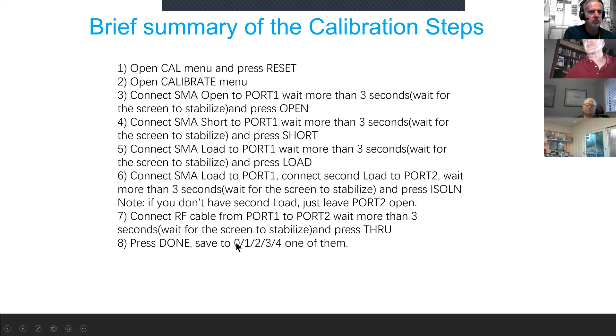And then connect an SMA load to port 1 and another to port 2, wait a few seconds, and press isolation. That second load isn't absolutely essential unless you're trying to measure a high isolation device. So if you don't happen to have a second load, just leave port 2 open. You connect an RF cable from port 1 to port 2 and wait a few more seconds and press through. Press done and save the data to one of the calibration registers 0 through 4. And there you are, you're calibrated.